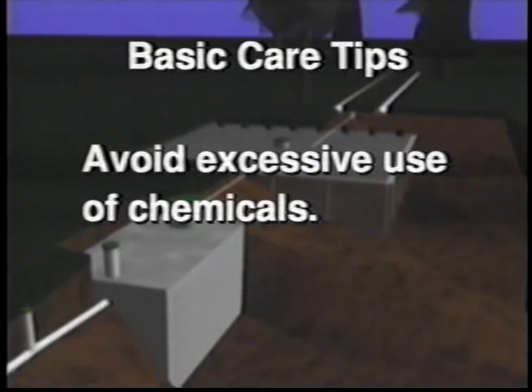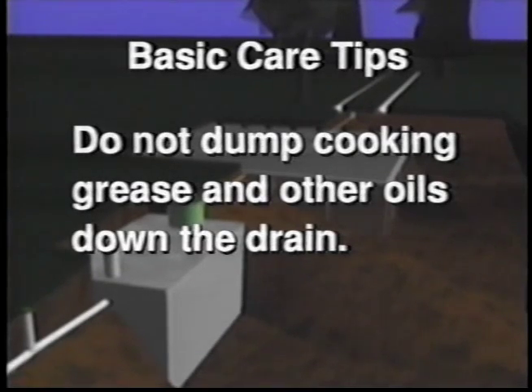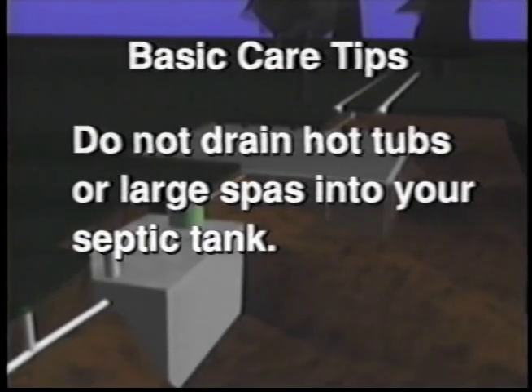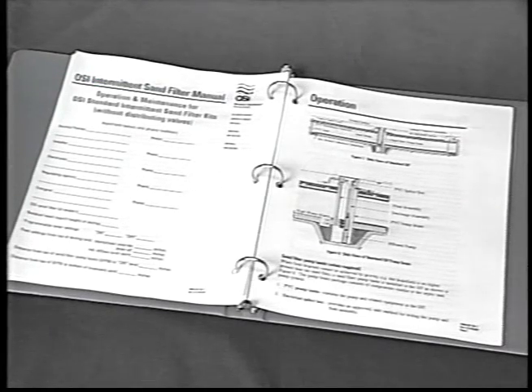Occasional use of bleach in laundry is acceptable, but avoid using automatic toilet bowl cleaners, which continuously feed bleach into the septic tank. Do not dump cooking grease and other oils down the drain — they will clog up an ISF or any other kind of on-site system. Garbage disposals should not be used, because they increase the need for tank pumping and general maintenance. Hot tubs or large indoor spas should not be drained into the septic tank, as the extra water may overload the system. If you use a water softener or water purifier, do not drain the backwash into your septic tank — it is safe to discharge it directly into the ground. A complete description of proper use and simple annual maintenance can be found in OSI's ISF Operation and Maintenance Manual.